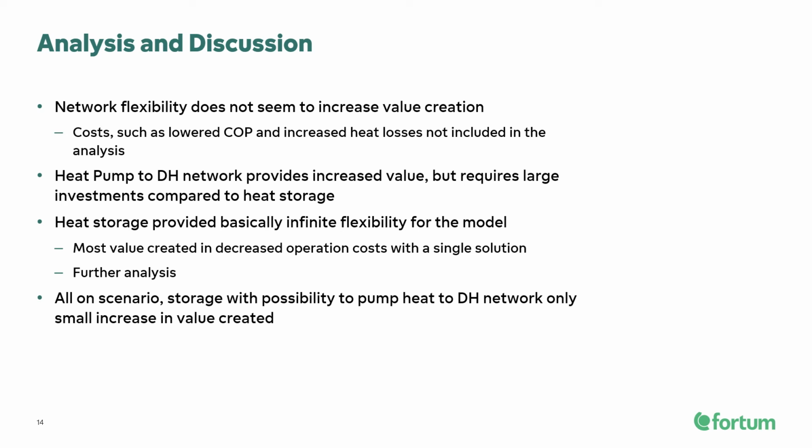to the heat storage. A heat pump unit is usually an expensive investment, and in this model and in this solution in the AltoWorks network, it doesn't seem to be a beneficial solution. Whereas the heat storage provided basically infinite flexibility for the model, since the storage was not fully utilized at any time. And we chose this scenario to be subject for a bit further analysis.